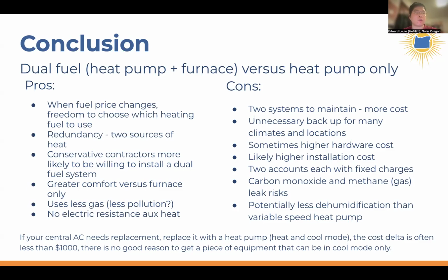You can still gain that additional comfort with a heat pump only system, but if you have a straight furnace system, you won't gain those greater comforts associated with the longer run times that you would with a dual fuel system. You certainly use less natural gas, and for the most part, there are very few scenarios where it would be more pollution, so it's almost always less pollution. And then in the few minutes out of the hour or few hours that a heat pump in winter goes into defrost, a heat pump only system would typically either blow some cold air or turn on an electric resistance auxiliary heat in order to keep the air warm during defrost.